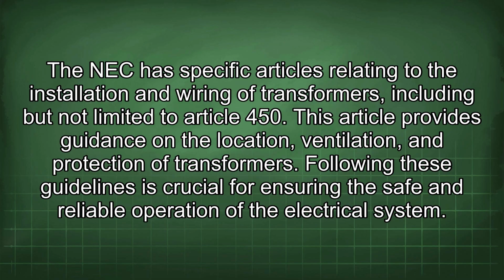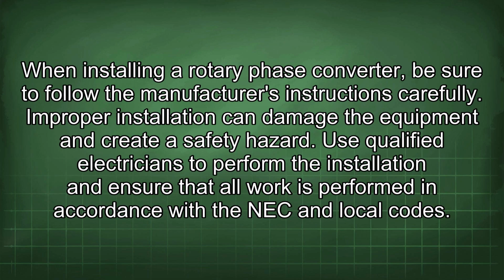The NEC has specific articles relating to the installation and wiring of transformers, including but not limited to Article 450. This article provides guidance on the location, ventilation, and protection of transformers. Following these guidelines is crucial for ensuring the safe and reliable operation of the electrical system. When installing a rotary phase converter, be sure to follow the manufacturer's instructions carefully. Improper installation can damage the equipment and create a safety hazard.